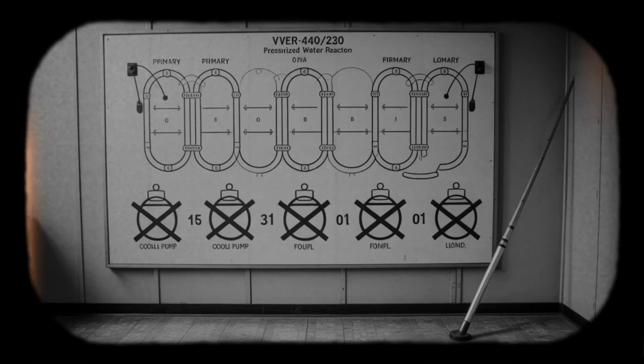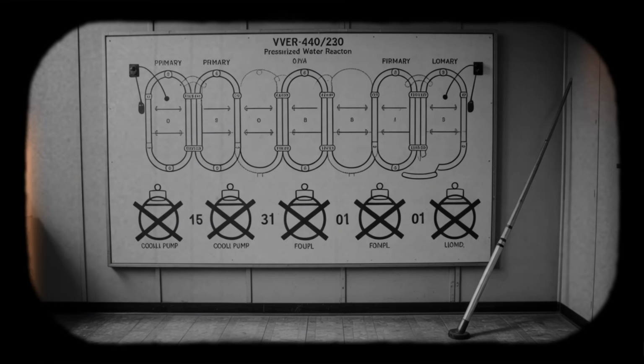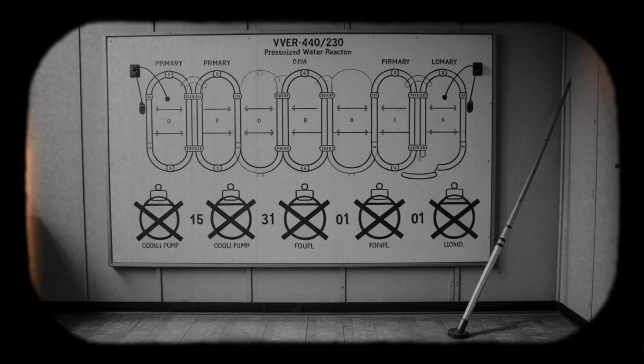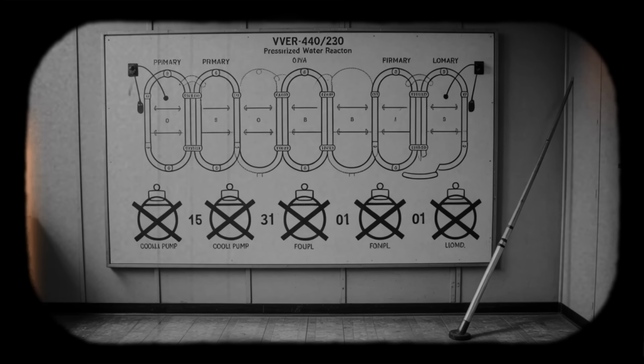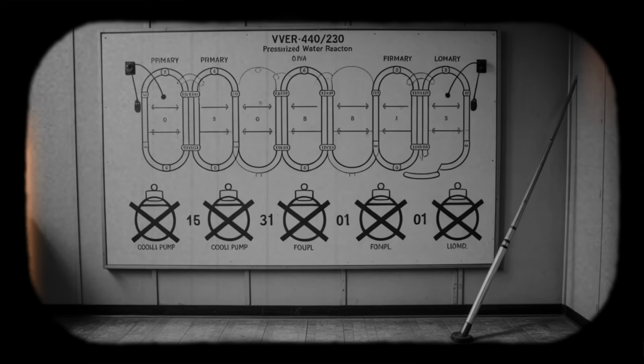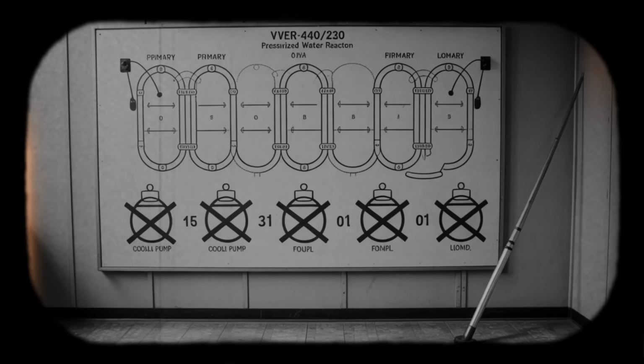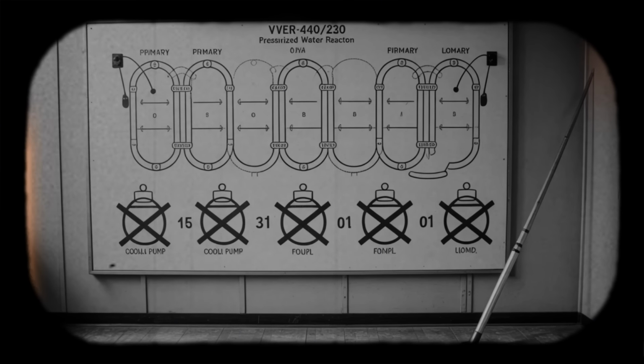That inventory could absorb heat through boiling, with steam released to the condenser or vented to atmosphere. This process bought time, several hours of margin, but it was finite. As steam generators boiled dry, heat removal would stop. Primary temperature and pressure would rise. Eventually, the pressurizer safety valves would lift to prevent overpressure.